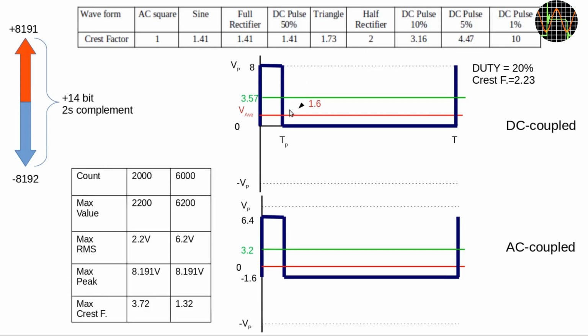Here, for example, is a sample DC pulse with 20% duty factor. This example works with volts, but the same principle holds for current as well. For a DC coupled device, the peak is 8 volts and its overall RMS is 3.57 volts. Thus, the UT210E has to be able to process and calculate the RMS shown by an AC coupled device, such as traditional AC multimeters, which is just 3.2 volts. So although we only see 3.2 volts on the display, the AD converter has to cope with 8 volts.